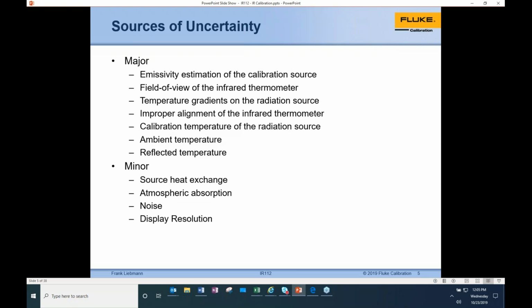Then we come down to the calibration, the radiation source. So again, I guess I misspoke. So there's the calibration temperature of the radiation source and then your emissivity estimation. So again, the calibrated temperature should come with the unit OEM. Usually it's expressed in a tolerance of a plus minus with an uncertainty associated to it. And then the emissivity estimation is usually stated also on the cal report.